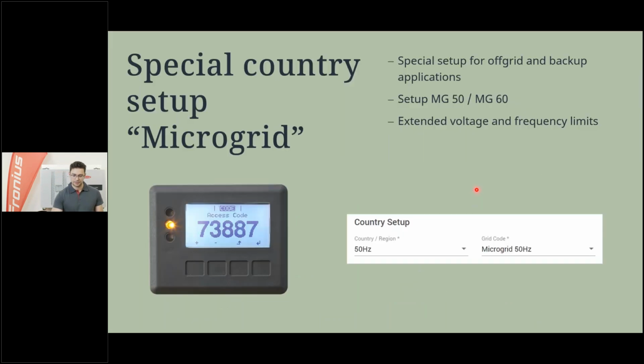All right. Last but not least, we have one special country setup that we need to select when operating in such a system together with DEIF. And this is called Microgrid. The Microgrid setting offers us an extended voltage and frequency limit in order to operate in such a system. And on a Snap inverter, it's very simple. You just go to the display of the inverter, enter here the access code. It's the same as for starting up the inverter initially. And you enter here MG50 or MG60 for 50 or 60 Hertz Microgrid.